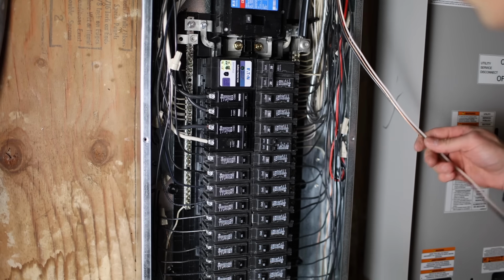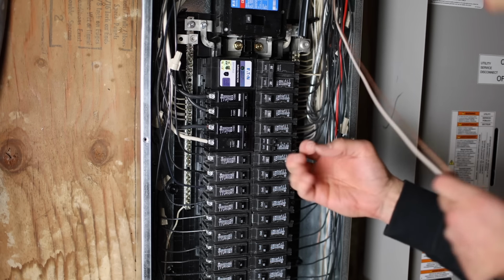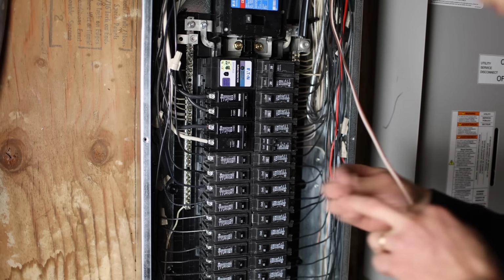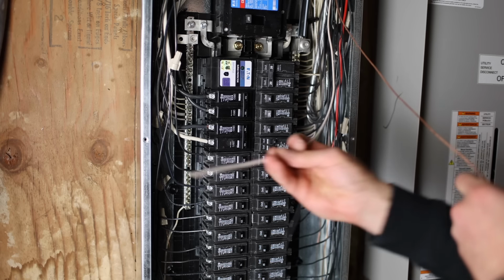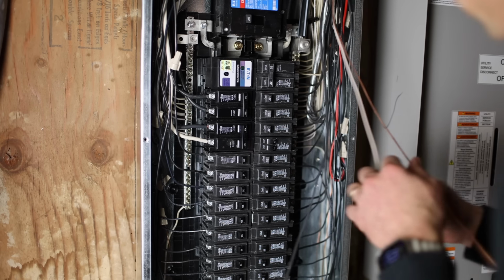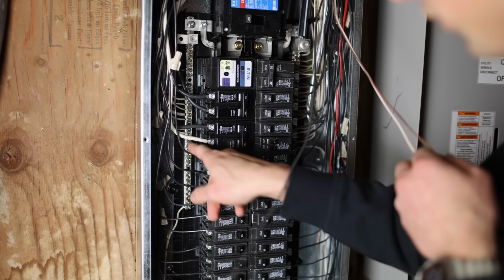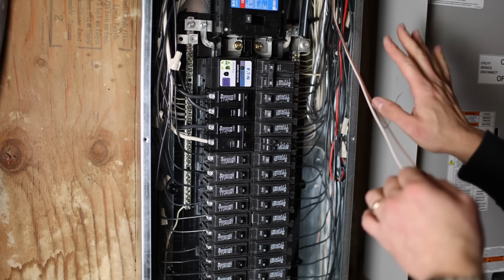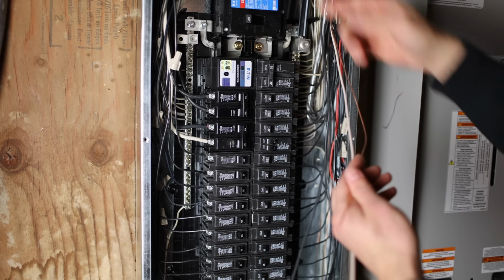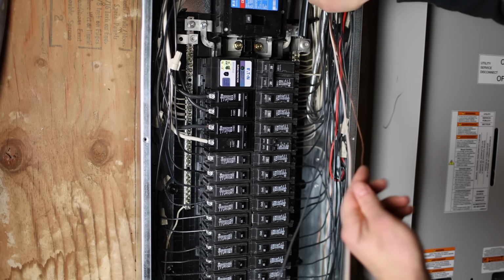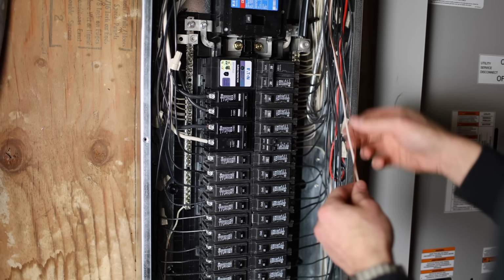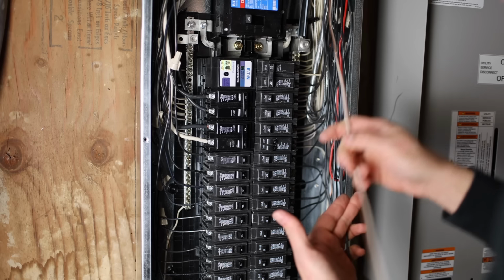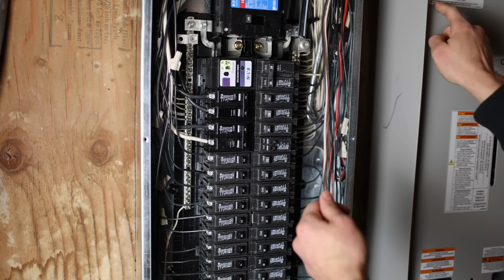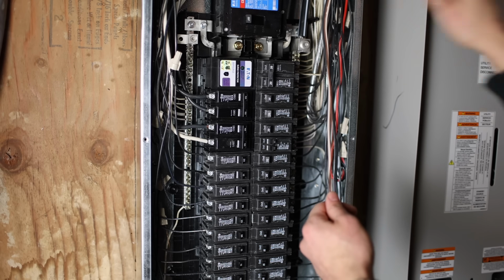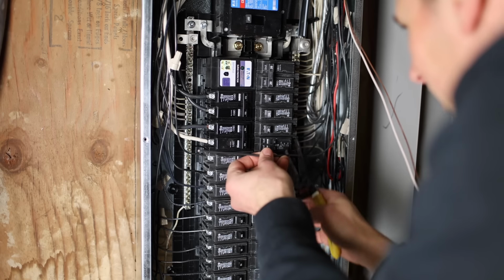And then hooking it up is fairly straightforward. The black wire goes to the breaker itself; this is where the power comes from. The white is the neutral, and that goes to the neutral bar right here. It could also go to this one, but I'm going to do it on this side, to keep it neat. And then the ground goes to one of the ground bars, which are grounded to the case of this. One thing about this panel is that the ground and the neutral are not bonded together, and that's because they are bonded together in the transfer switch, and you can't bond them in both places.